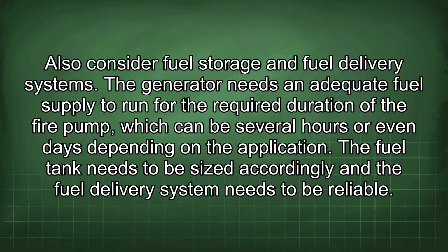Also consider fuel storage and fuel delivery systems. The generator needs an adequate fuel supply to run for the required duration of the fire pump, which can be several hours or even days depending on the application. The fuel tank needs to be sized accordingly, and the fuel delivery system needs to be reliable.